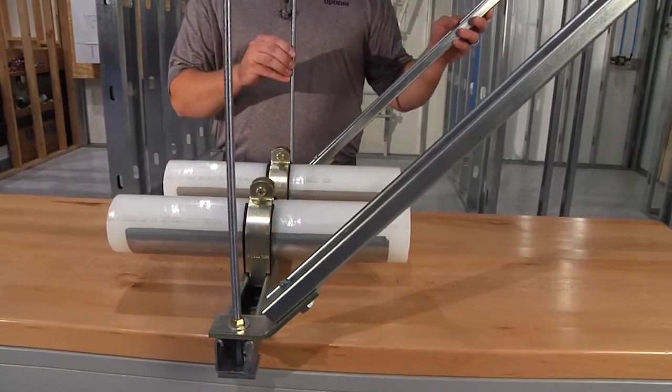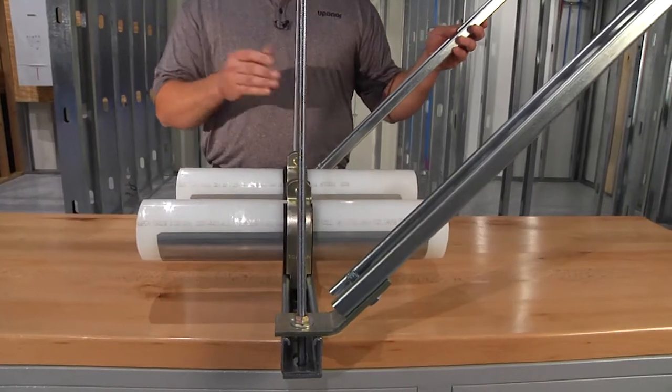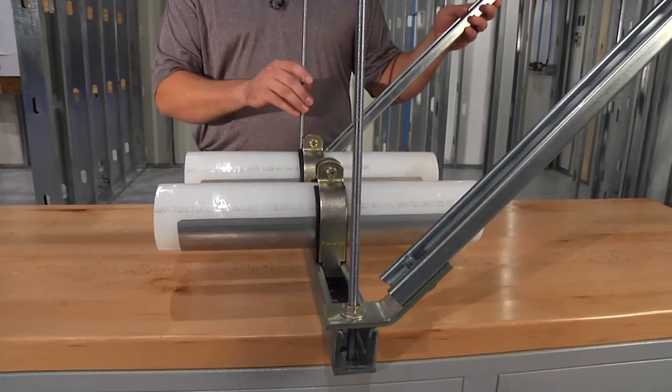The fixed anchor point is going to be utilized every 65 feet for hot water scenarios and every 150 feet for cold water scenarios.